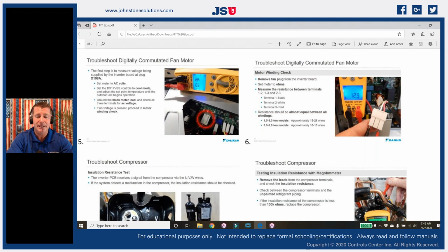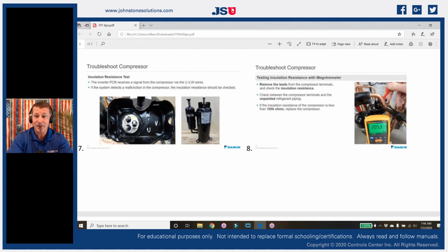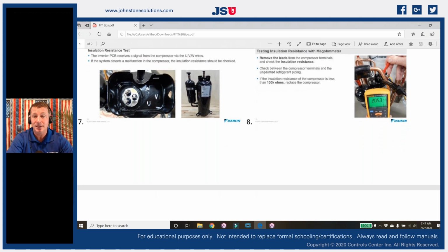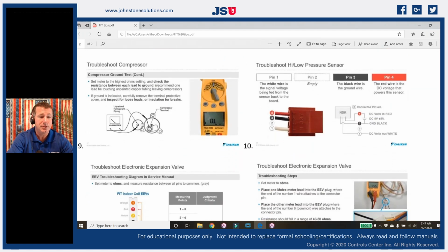So very simple design in our inverter technology. If we look at our compressor, same thing. Our compressor, remember, all compressors are a vapor pump being driven by some type of locomotive force. So in our residential and unitary HVAC products, we're using a vapor pump that is being driven by a motor. So we just took out that permanent split capacitor motor and put in a 3-phase motor. It's as simple as that. So instead of seeing those C, R, and S terminals on your permanent split capacitor compressor, we're just going to have U, V, and W. That's our 3 phases. And the same way with those, we can test those between each terminal just like on those condenser fan motors, and we're going to have the same resistance between those. And then we can check, of course, to ground. We're always going to mega ohm the insulation on our motors. So we're going to mega ohm the insulation going to ground on our compressors, just the same. So that's all we're going to do.